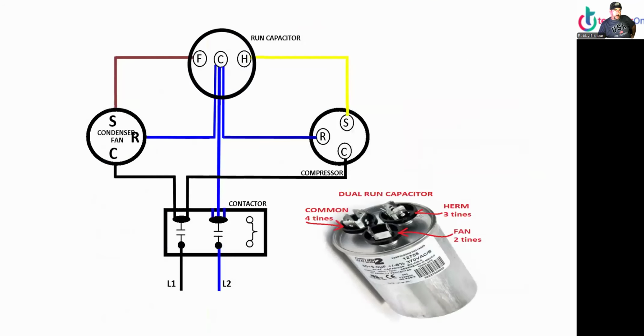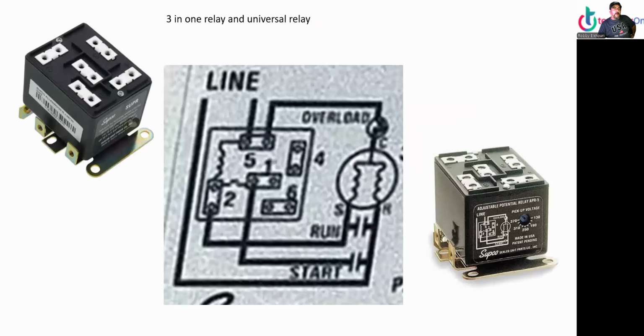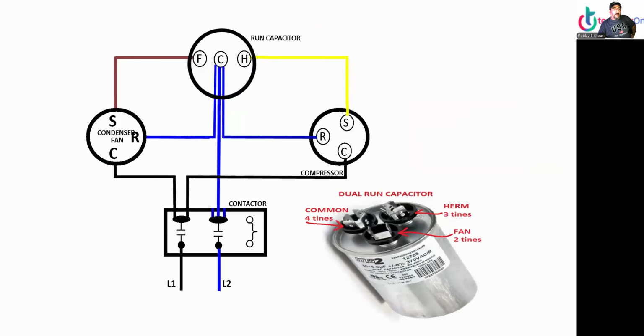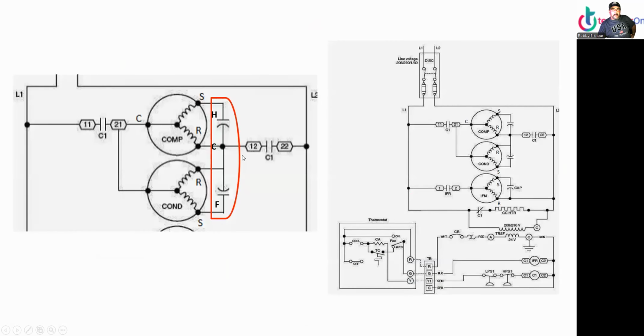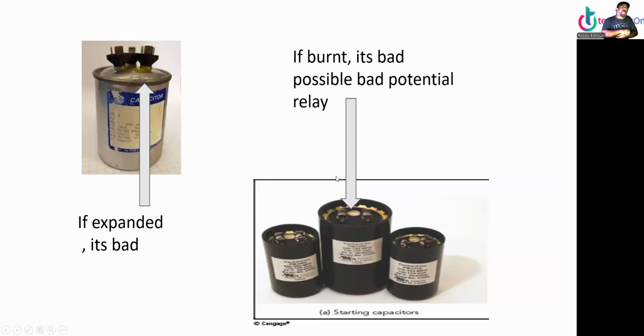Okay. Now let's move on. This is the universal relay. Since we're talking about capacitors and stuff, this is some ACs, simple, no relay, no nothing, just capacitors. This is a picture of a dual capacitor in a diagram. If it's burnt, it's bad, possibly a bad potential relay. Most of the time, if it's a burnt capacitor, it's a burnt potential relay. If expanded, it's bad. Look at that, expanded.